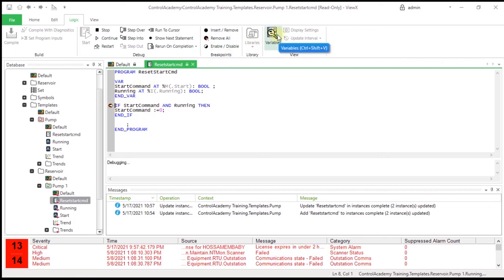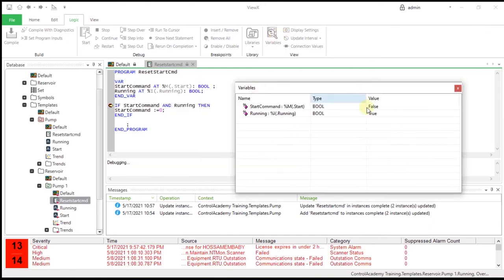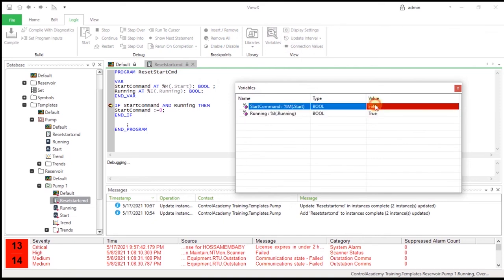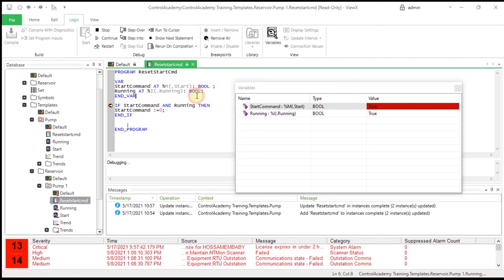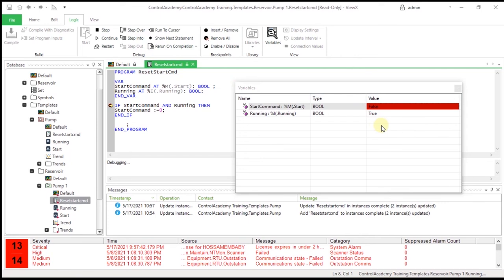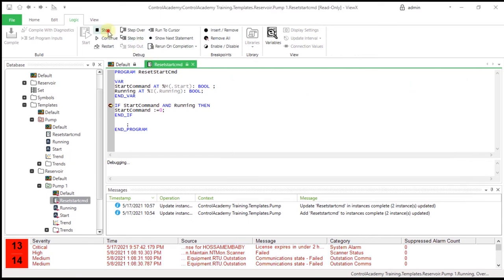From the Logic tab, select Variables on the ribbon. Change the start value to true and running value to true. Use the step into feature to step through the code and verify that the code executes as expected using the yellow indicator and the variables display. Close the variables window, stop debugging, and remove the breakpoint when you are finished.